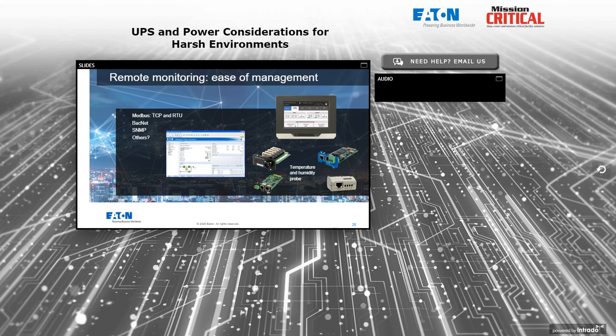Okay, so ease of management, we've talked about this a little bit already. First of all, the display on the front of the UPS should be rugged, should be resistant to water and corrosives and things like that. It should have a reliable action to it, either haptic sensitive buttons or touch sensitive color LCD screens that allow you to do more and see more and provide more metering and more alarm and status information than you would find with the traditional front panel, which might have LED lamps and a one-line diagram printed on it in paint. That kind of technology has kind of gone by the wayside in all UPS applications.